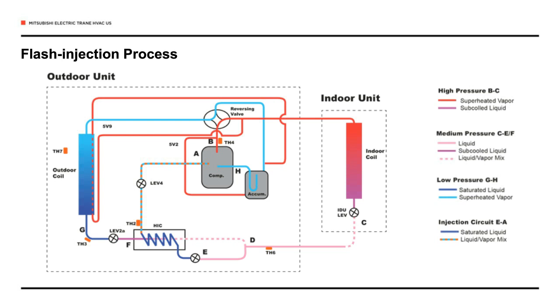The liquid then travels through another linear expansion valve, shown at point E, and through a heat interchanger circuit where it's actually absorbing heat from the other hot gas that was coming off the top of the gas-liquid separator. And then that goes up and through another linear expansion valve, LEV4, where we're metering that mixed phase refrigerant into the dome of the compressor. So we only put as much in there as we need to do as much cooling as we need, so that we don't cause that compressor to overheat. So that's essentially how the flash injection process works. We're metering a mixed phase refrigerant into the dome of the compressor to cool it down so we can run it at higher speeds without causing any sort of failure in the compressor.